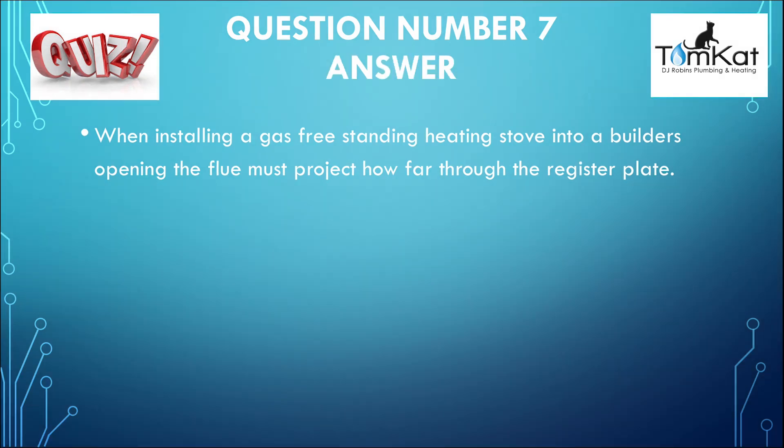Now the answer for question number seven: when installing a gas freestanding heating stove into a builder's opening, the flue must project how far through the register plate? The answer is B — 150 millimetres. That was the answer for question number seven.